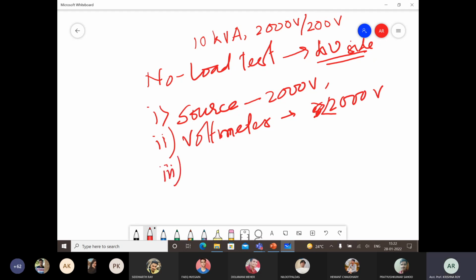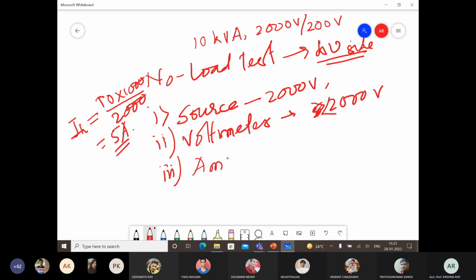Number 3, so let us find the high voltage side current IH, that is 10 into 1000 divided by 2000. Okay, so that is 5 ampere. So this is the rated current, and the exciting current is about 2 to 6% of this 5 ampere. So that is a very small current. So we require one ammeter with very low range. Okay.